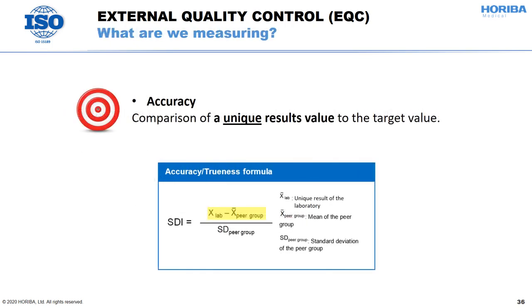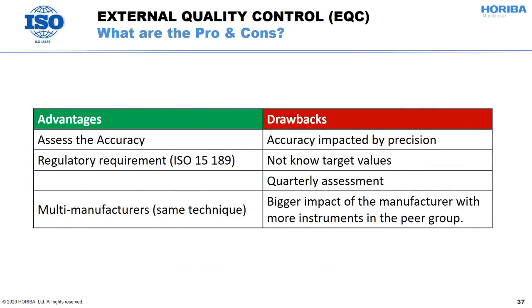What are we measuring? The accuracy is calculated as the trueness, except that it is a unique value — not the mean — which is compared to the peer group. What are the pros and cons of the EQC? This external quality control is a regulatory requirement and allows to assess accuracy. But accuracy could also be impacted by poor precision. Unlike the externalized IQC or QCP, the external quality control is done quarterly, which is a long period without any assimilated true value comparison. And if a manufacturer is over-represented within the peer group, it could have a bigger impact on the true value definition.